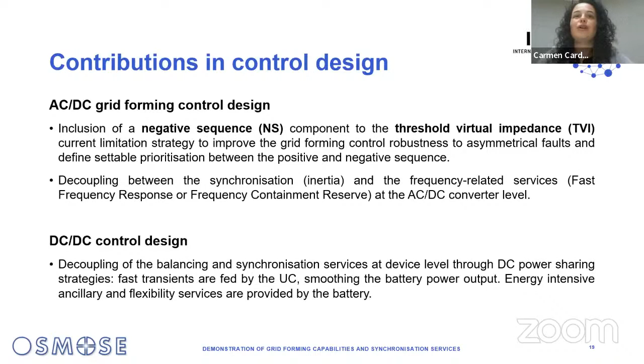In fact, if you have heard about grid forming, you will know that one of the main challenges of this type of control is that converters are quite sensitive to high currents and they need to be protected. One technique is using this threshold virtual impedance, and at the moment of the project there was little research on the behavior under asymmetrical faults, and that was a contribution that Ingeteam proposed. Also, we worked a lot on the decoupling of these synchronization services, which for us is inertia, from the frequency-related services, those that can rely on the measurement of the frequency, like frequency response or frequency containment reserve. This can be achieved not only at the AC-DC converter level, but also at the DC device level. We can have power sharing strategies that decouple the balancing services from the synchronization ones, such that the battery does the balancing services and the synchronization services are handled by the ultracap. So now I leave the floor to Markel to tell us more about how we can achieve this performance.